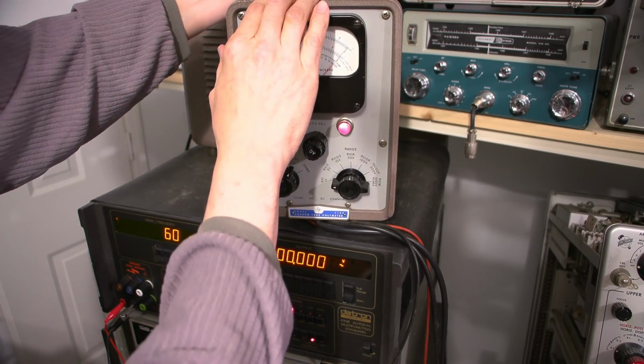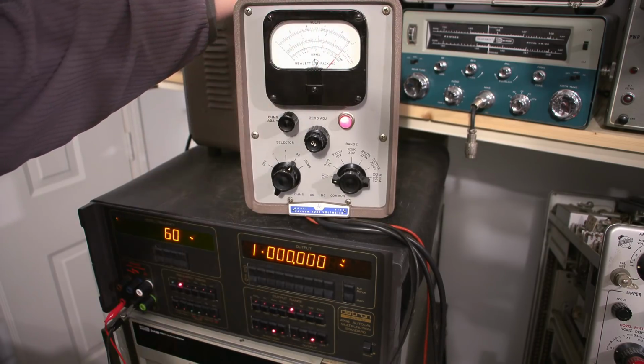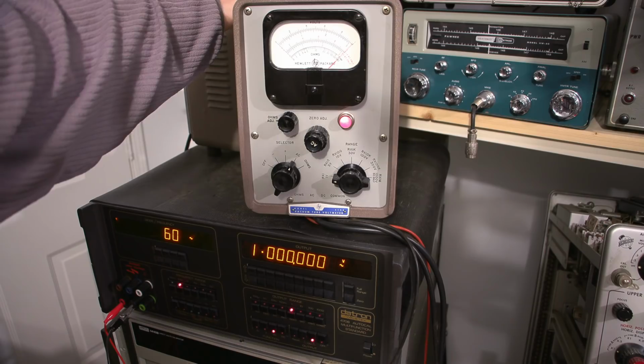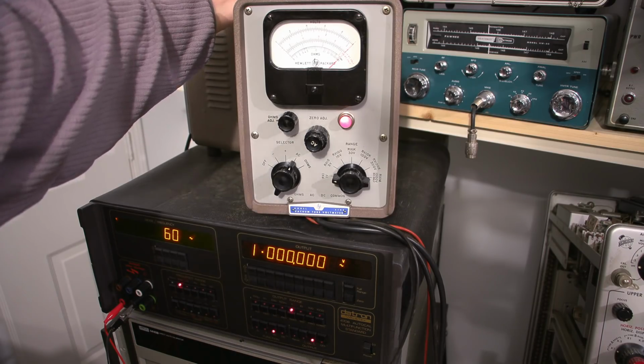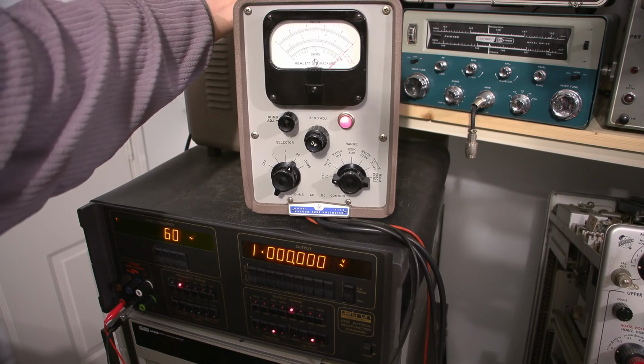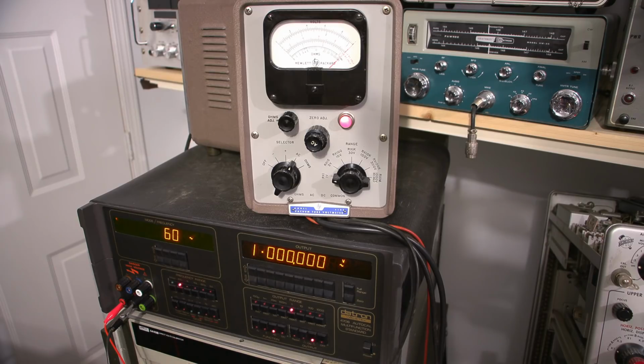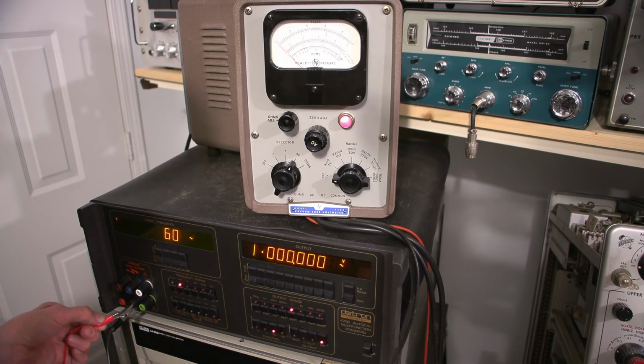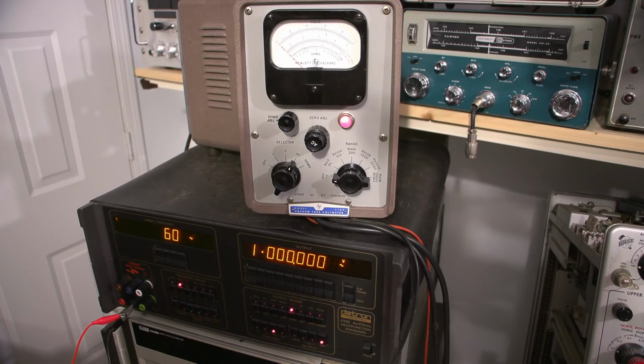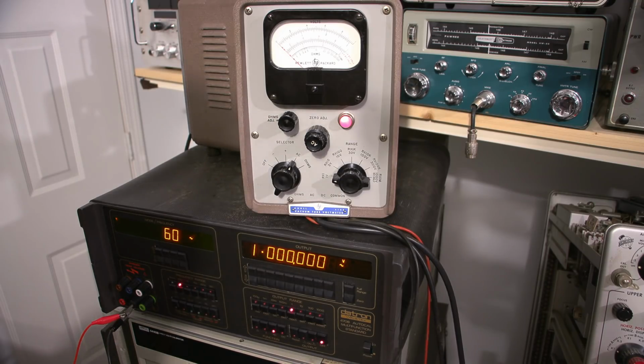So now what I need to do is move that up to the 1. So hopefully I can do this from this angle. Right about there. Right on the number 1 to my eye. Yep, right on the number 1. So what I'll do is I will shut this off. There. And I will ground the probe out here again. Or hook the common to the center anyways. And that's right on 0. So that scale is now calibrated.